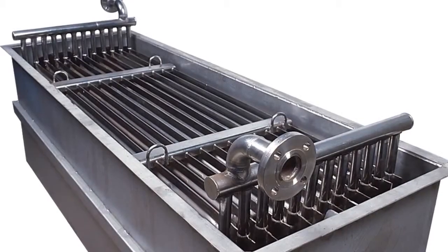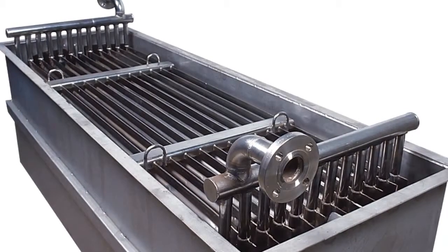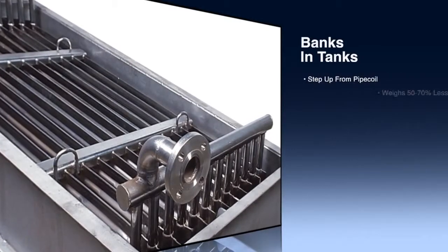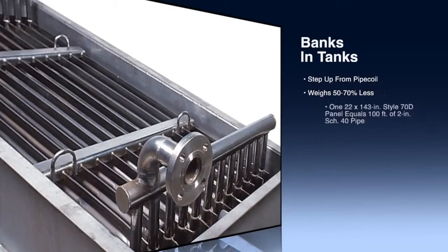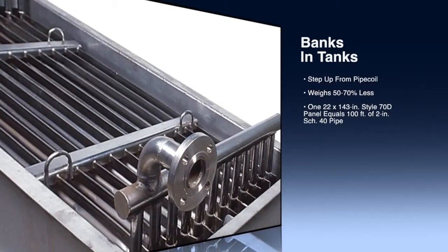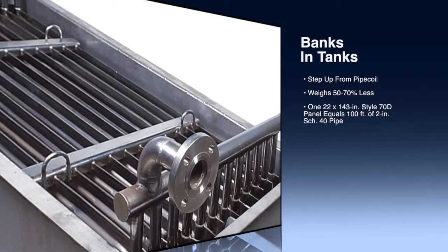In tanks, compact Plate Coil Banks offer at least twice the surface area in a given space, at half the weight as equivalent pipe coil. As immersion heaters, the Plate Coil planar shape induces a chimney effect for natural convection circulation and improved heating uniformity.